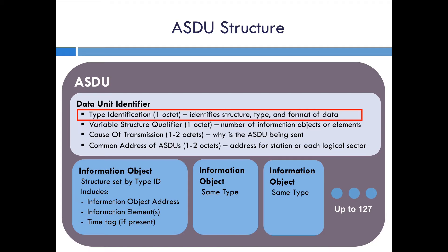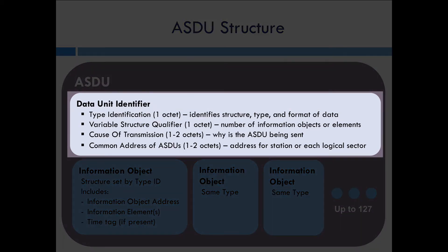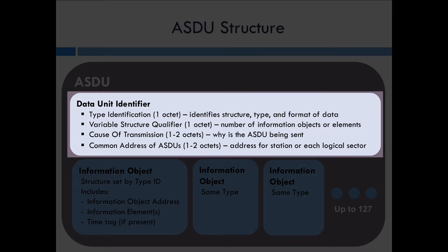If you look at how the ASDU is put together, there's always a data unit identifier. This identifies what type the ASDU is — basically it describes the format of the data, what's included, and the basic types of data included in the message. It also has the VSQ, or variable structure qualifier, which identifies how many objects are in the ASDU. You can also have the cause of transmission, which is why the ASDU is being sent.